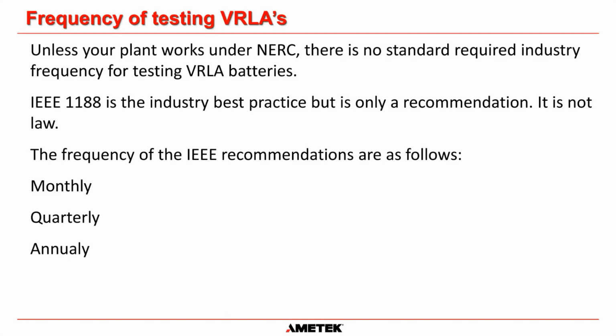So the frequency of testing for VRLA batteries, we go to IEEE 1188. Now remember, IEEE is only industry best practice. It's only a recommendation. It is not the law. Okay, so it is a standard, but it is not the law. And the frequency of the IEEE recommendations for valve regulated batteries are as follows: monthly, quarterly, and annually. That is what IEEE recommends for portable testing.